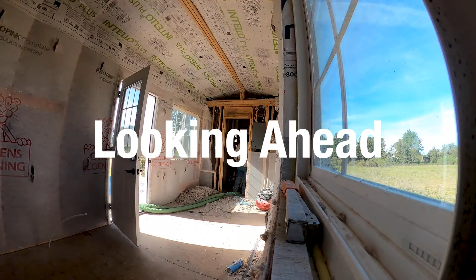The electrical code tells you what size wire is good for what amperage. Now, there is something to keep in mind. If you have a long distance, then you can't use those numbers. We're actually running this power all the way back to the panel on the house, and that's how we're getting power in here. But we can't use this 6 gauge wire all the way back to the house because it's such a long distance, and the wire is going to heat up. There's going to be more resistance, so use a bigger wire. And there are wire sizing calculators online. This wire is made by a company called Southwire, and if you go on their website, there's a wire size calculator. You can type in the current, you can type in the distance, and it'll tell you what kind of wire you can use.